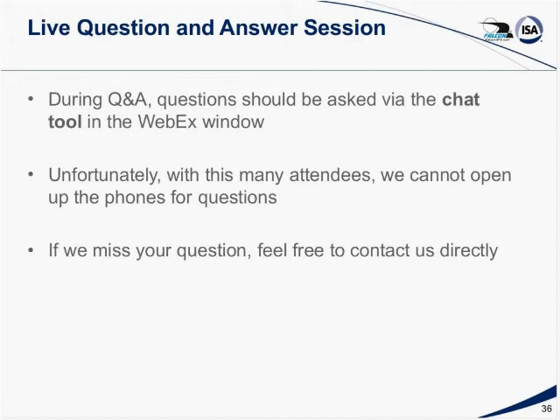C. Mike, why don't you give them the example of the FasTrak that's out here in Los Angeles right now? Yeah, we're powering all of the toll road RFID and camera systems. The RFID systems are used for automatic payment on the toll roads. The UPS is sitting in a NEMA 3R enclosure, and they want 72 hours of backup. So we have 3 large 40 amp hour battery banks inside that enclosure along with our UPS. And in the event of a utility loss, or in the case of Los Angeles, an earthquake, they have 70 hours of backup. Thank you, Mike.